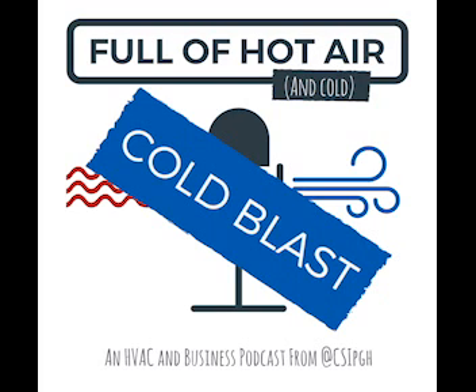Right. Now, there's a communication going back and forth where they're talking, but all that is provided by the outdoor unit. So the first thing I'm going to do is have the guy go out to the outdoor unit and simply take a reading. We have three wires going between a Mitsubishi system, marked S1, S2, S3. S1 and S2 are typical 208/230 high voltage. The unique part of what Mitsubishi does is they use S2 and S3 for their DC communication. So we're actually sharing the S2 leg with high voltage and DC voltage.